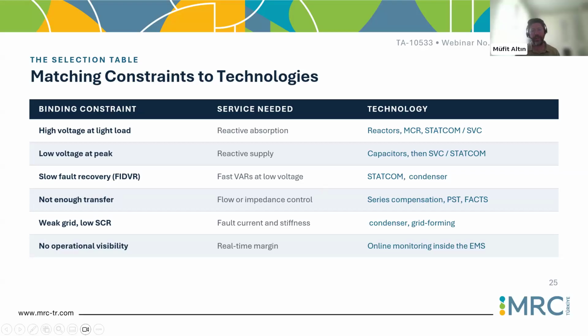So if you have a weak grid at the connection point where the wind farms or other renewable generation connect, you should be very careful how you put the requirements into the grid, even for the fault ride-through. In Australia, for instance, they also have other types of problems, like multiple fault ride-through. When lightning hits the lines, it could create consecutive fault cases, around 10 or 15.